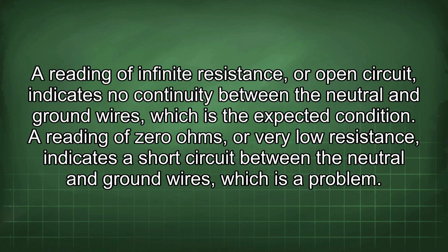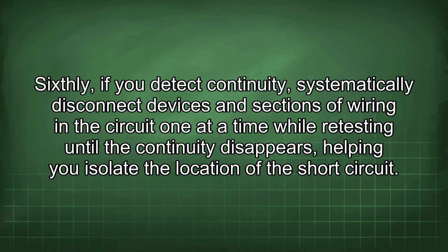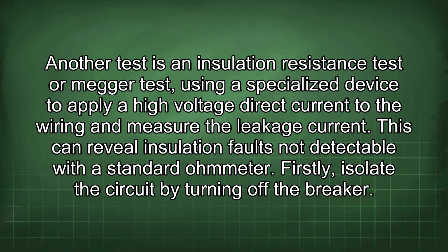A reading of infinite resistance or open circuit indicates no continuity between the neutral and ground wires, which is the expected condition. A reading of 0 ohms, or very low resistance, indicates a short circuit between the neutral and ground wires, which is a problem. Sixthly, if you detect continuity, systematically disconnect devices and sections of wiring in the circuit one at a time while retesting until the continuity disappears, helping you isolate the location of the short circuit. Another test is an insulation resistance test or megger test, using a specialized device to apply a high voltage direct current to the wiring and measure the leakage current. This can reveal insulation faults not detectable with a standard ohmmeter.